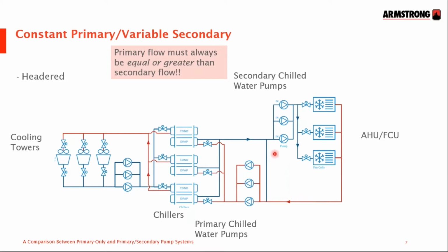The bypass loop, the mixing header, it's got to be big enough and long enough so that the warm water here doesn't find its way back into the cold water here, and it's got to be large bore enough so that the pressure loss from one end to the other is very low, so that the water just once again isn't pulled through or pushed through from this end here.